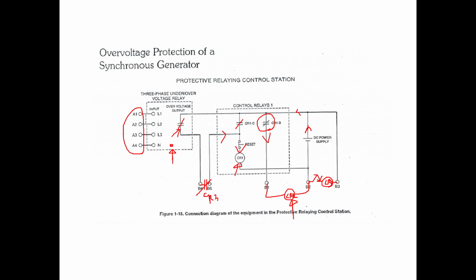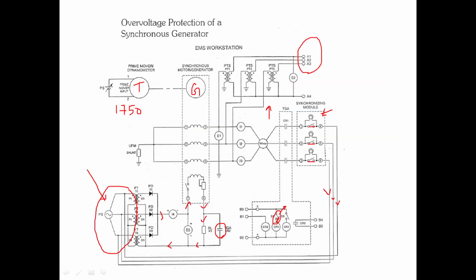When this is open, CR2 is de-energized. When CR2 is de-energized, this contact is open and the current flows through the resistor. So the control action is to insert the resistance in the excitation circuit. When you insert the resistance, the excitation current is reduced, and then the over voltage is reduced and it becomes the normal voltage. Thank you.